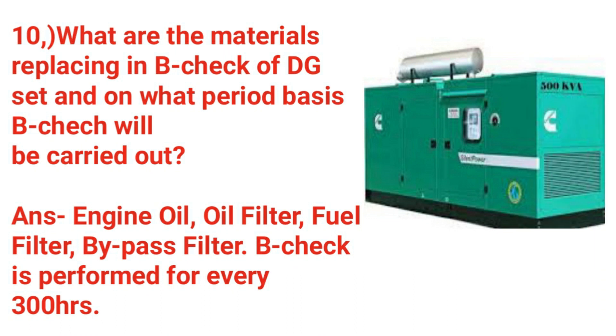What are the materials replaced in a DG set B-check, and what maintenance is carried out? Engine oil, oil filters, fuel filters, and bypass filters are replaced. The B-check is performed every 300 hours.